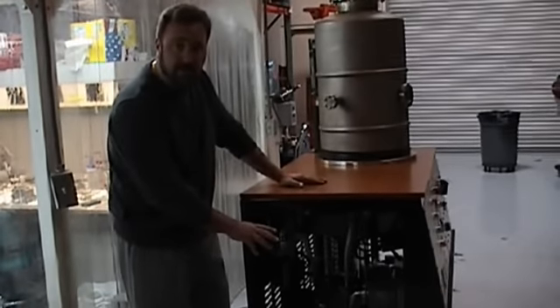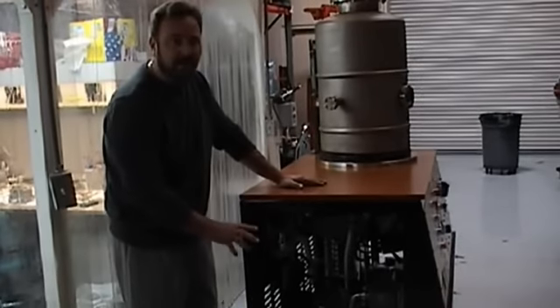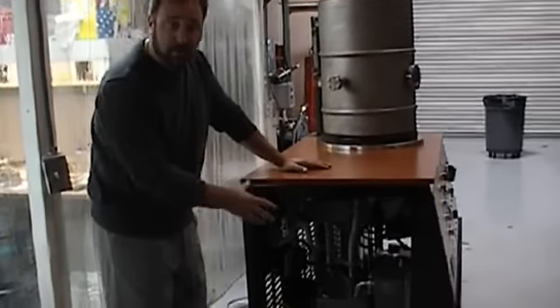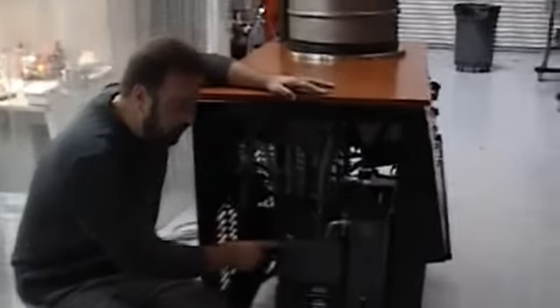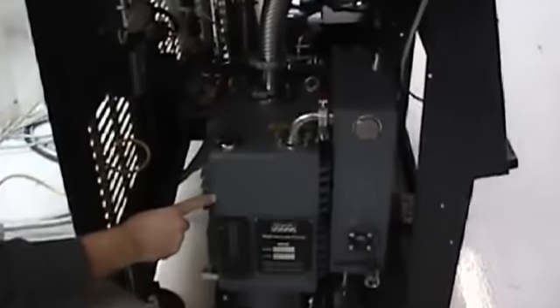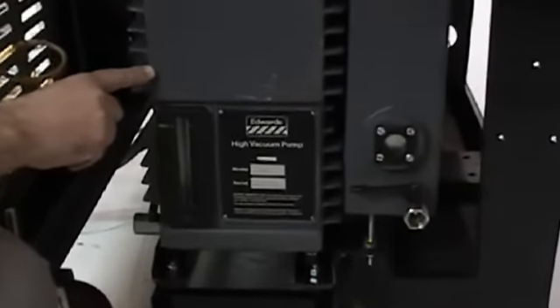What we're here to show you is some of the components located underneath the cabinet that you can hear operating, but now we're going to show you. What we have here first is our Edwards high vacuum pump. It's a 25 CFM, 2-stage rotary vacuum pump. We've included a high efficiency oil mist eliminator built right into the cabinet.